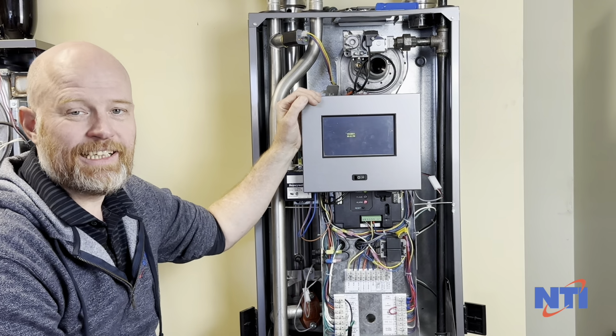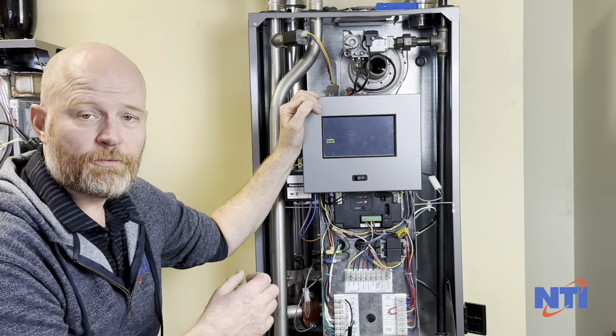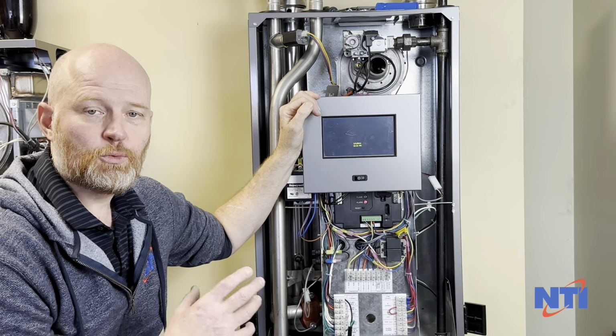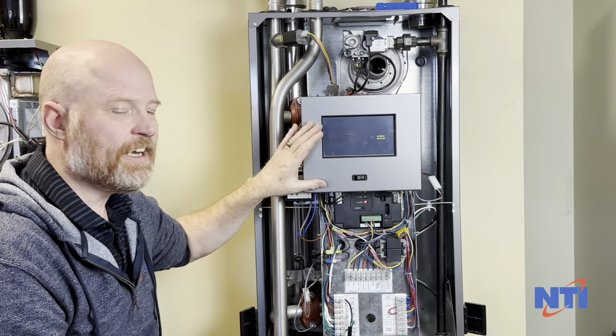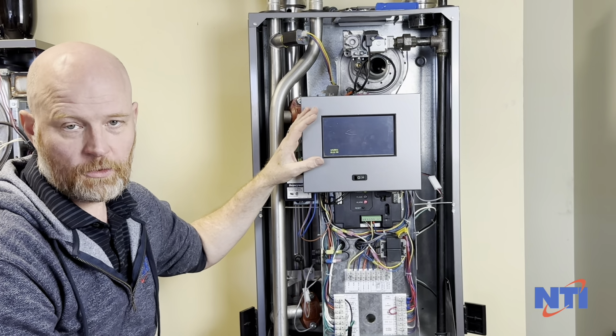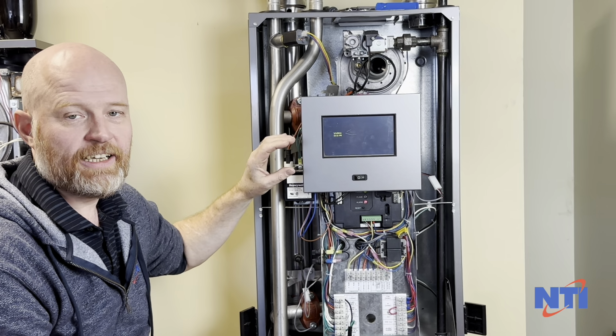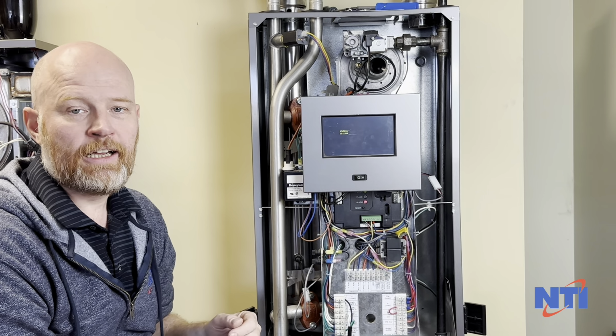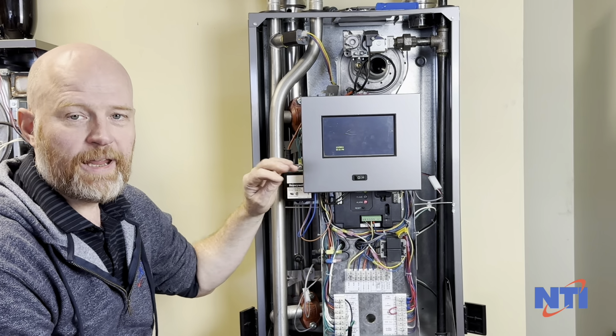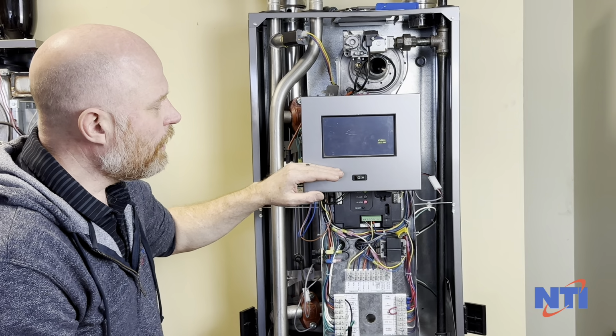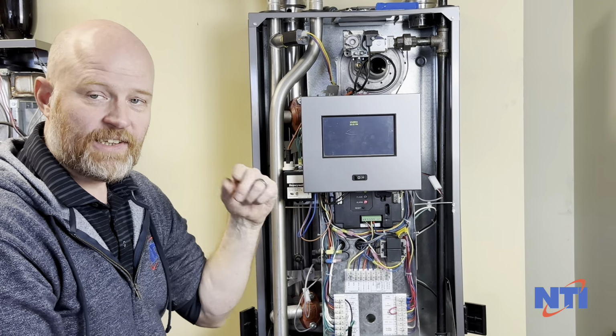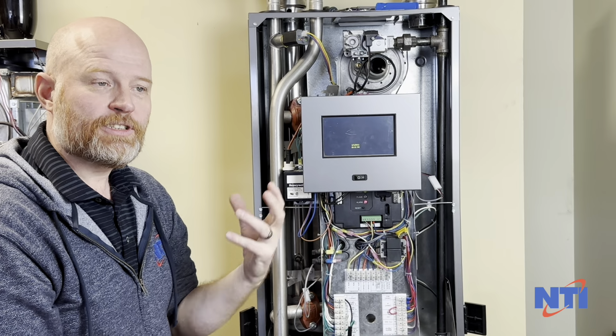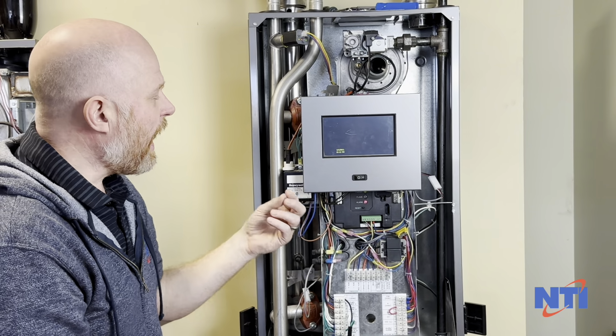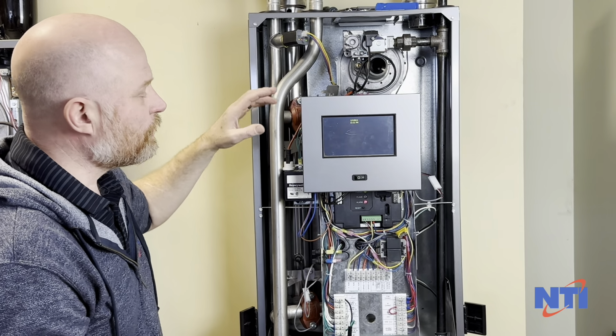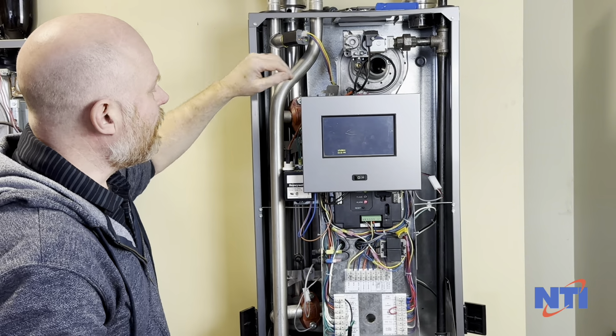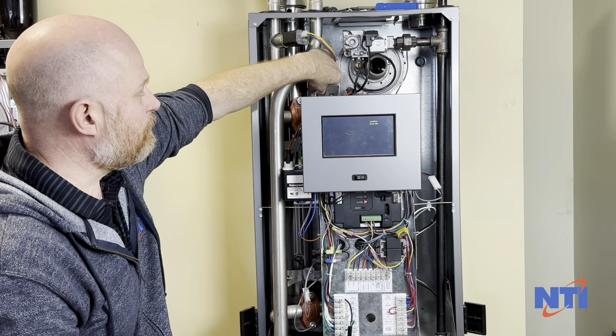If you've got a boiler that is lighting, so you get a flame in the chamber for only 2 or 3 seconds, but the boiler just will not stay lit, and you'll either get an ignition failure error code like a 109, you may get error codes indicating flame lost during run, flame too low, anything along those lines. What that indicates is the boiler is actually physically getting the burner to light. It just can't keep it lit for some reason. And the primary reason for that is the boiler can't see the flame. The way it sees the flame is through your flame probe.